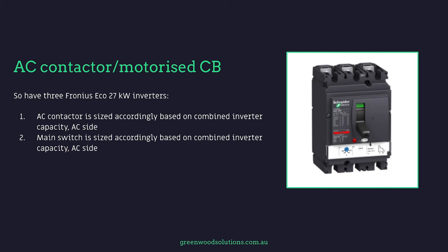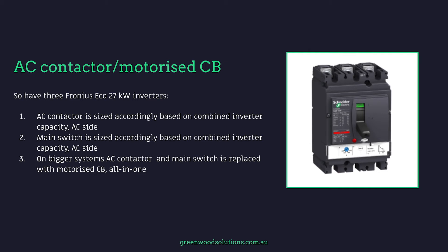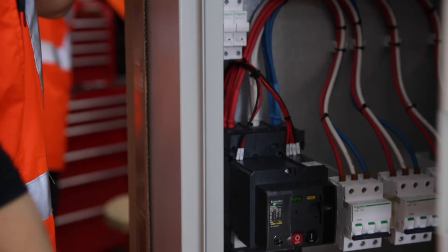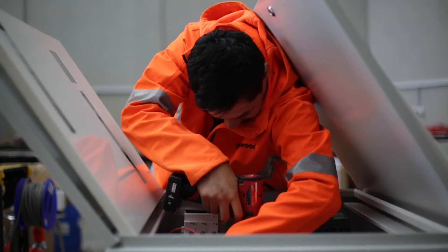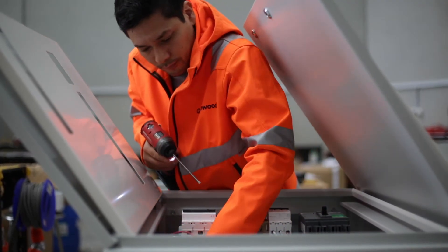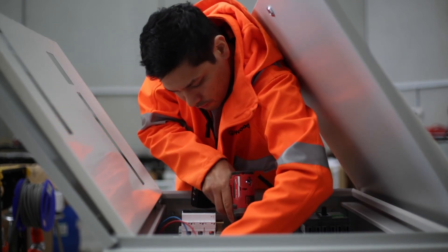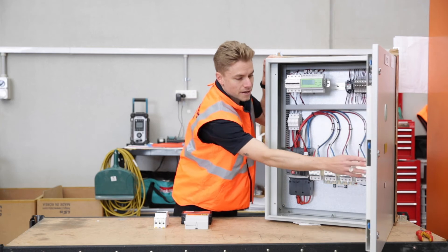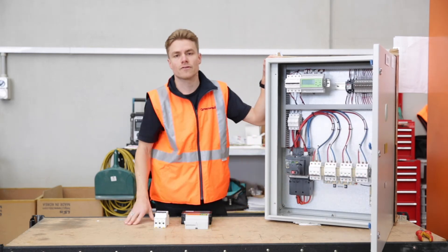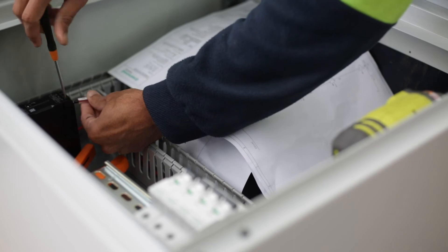The main switch is also sized accordingly based on combined inverter capacity on the AC side. On bigger systems, the AC contactor and main switch is replaced with a motorized circuit breaker — an all-in-one approach. In our case with our GridSafe GS100, we've incorporated the AC contactor and the main switch into one unit, using a 160 amp motorized circuit breaker. This means fewer components inside the board, which allows the installer more room for cabling and taking into consideration bending cable radiuses.